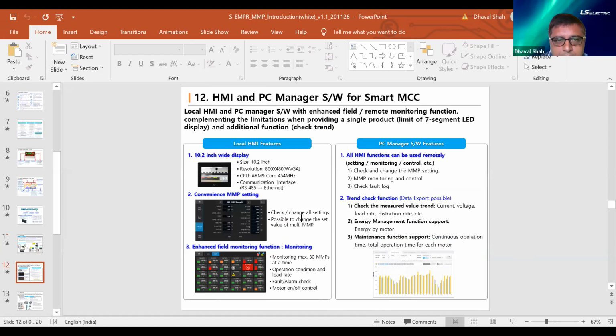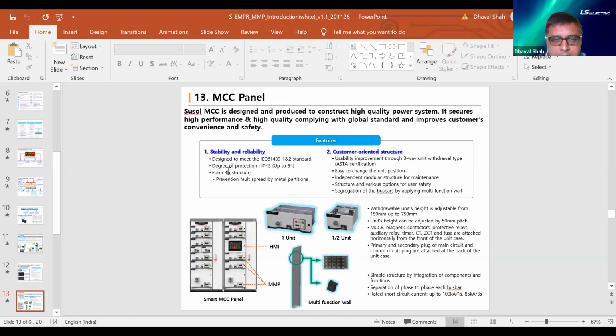So this is the HMI which we can offer. Where settings are, if you have the software, you can copy paste the settings. So again, configuration time is reduced, and at the same time, human errors can also be avoided. This is the snapshot of an intelligent MCC, with reduction in the CT, reduction in the meters. Compactness, almost 30% reduction can definitely be achieved through any intelligent MCC.